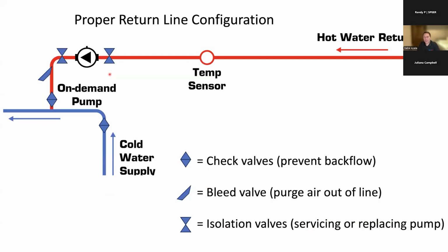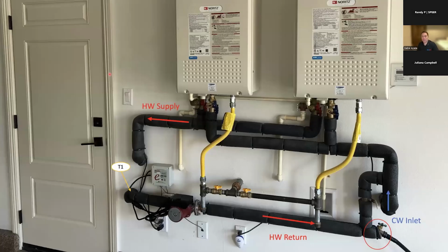And then on the return line, there are certain things that you need to incorporate too, such as check valves to prevent backflow, a bleeder valve or a hose bib to purge air out of the line, and an isolation valve so that you can maintain the pump and replace or service it. So here's what it looks like on a typical recirculation loop for a house. Here we see this house has a couple of tankless water heaters. You have the cold water coming in here, feeding into these 2 tankless, and then here's your hot water supply going out to the house. And then here below it is the return line. So this completes the loop.